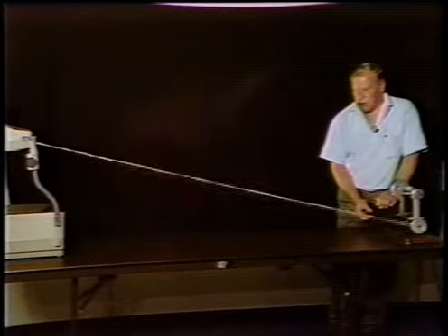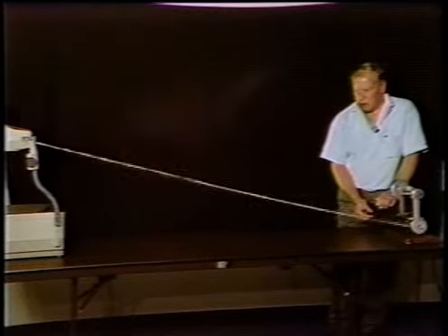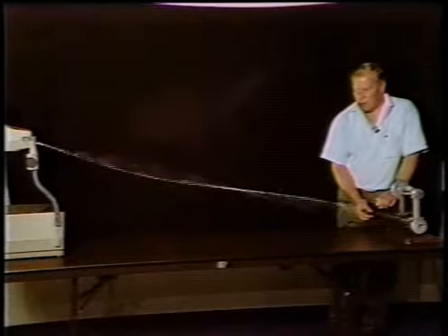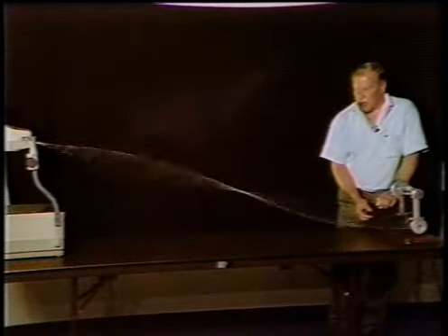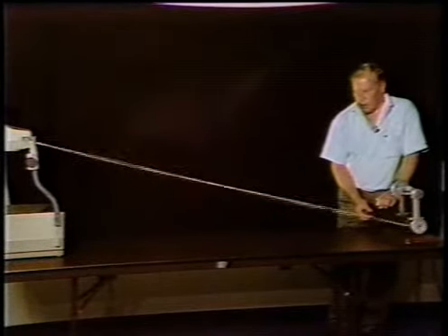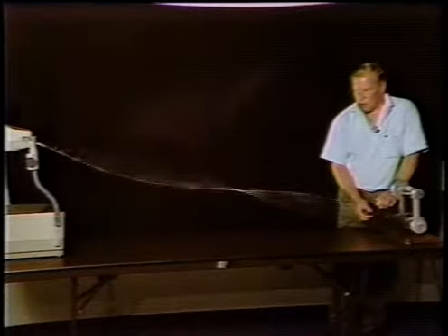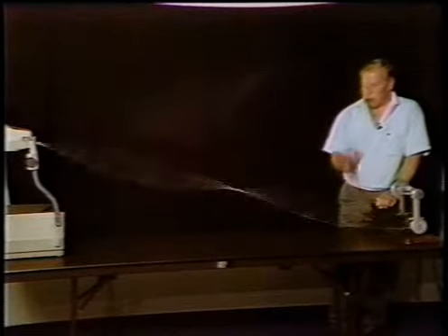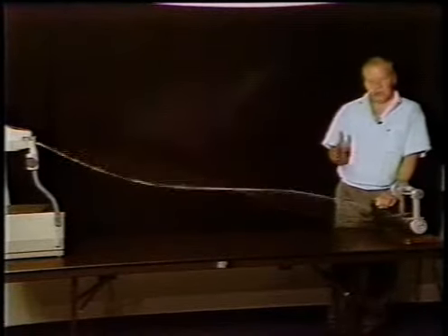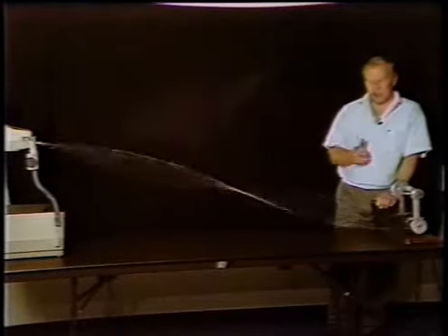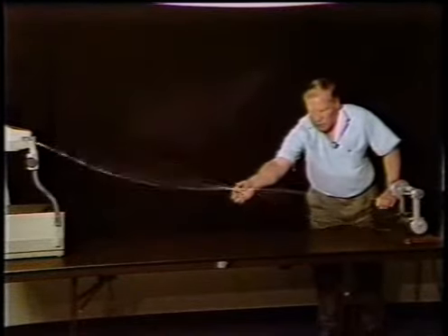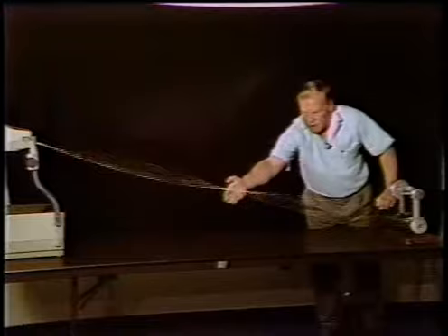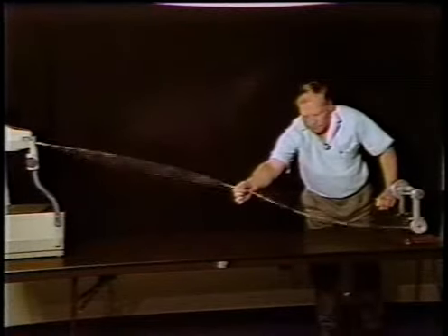I'm going to continue to increase the rotating speed, the exciting force frequency, and as you'll note, we reach another rotating speed or frequency. This is referred to as the second bending mode of resonance. And basically what this system has done is it's split itself now into 2 separate spring mass systems, separated at this point in the center, referred to as a nodal point.